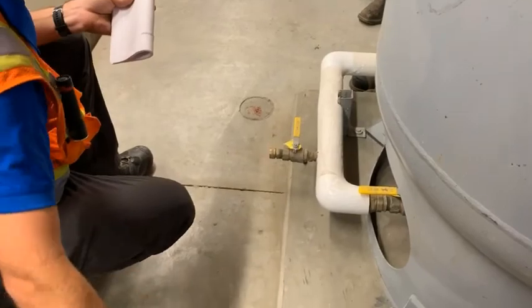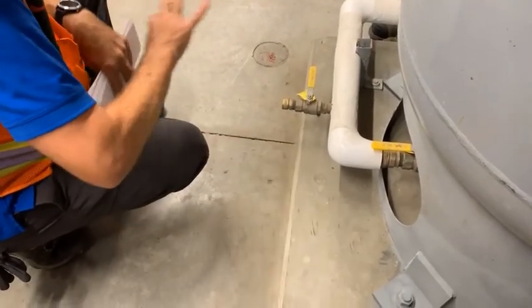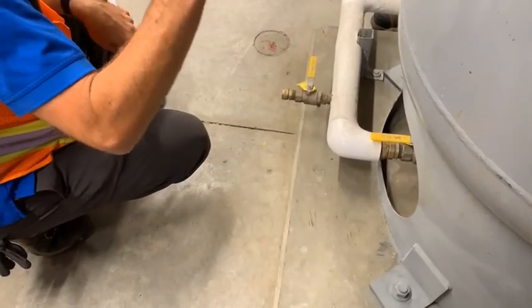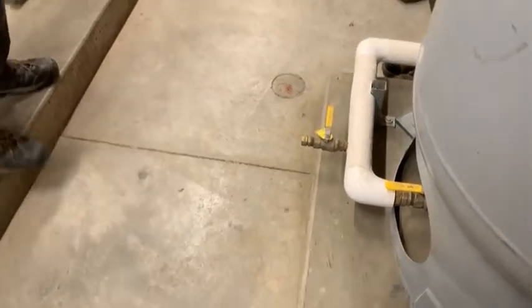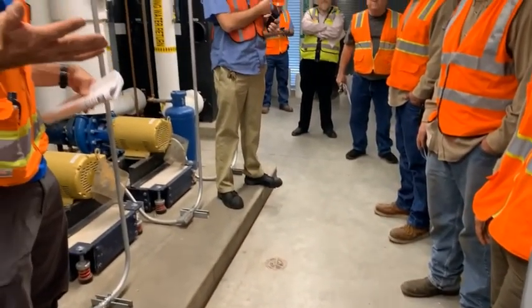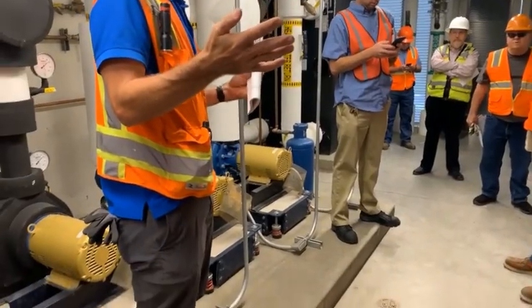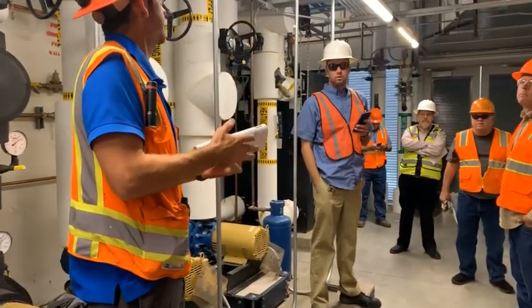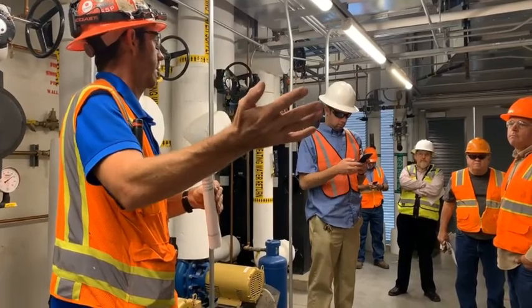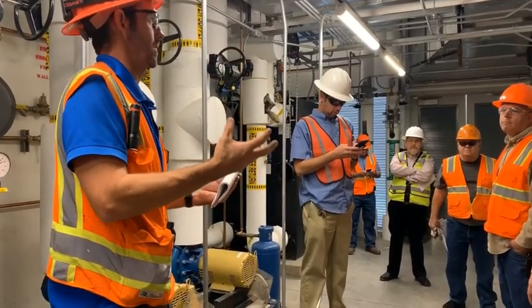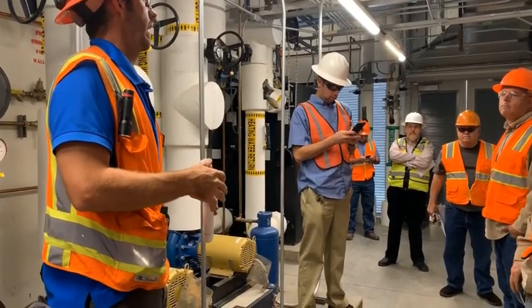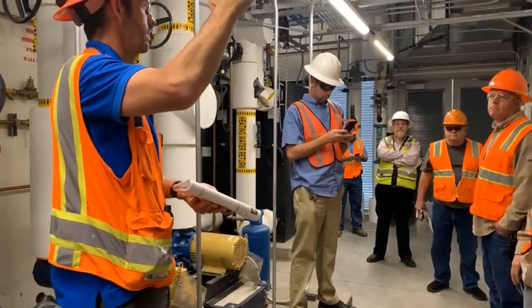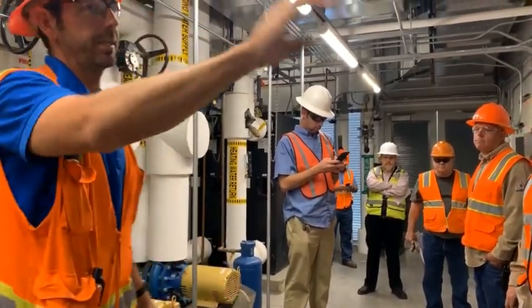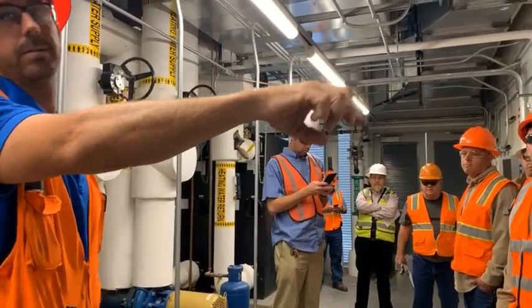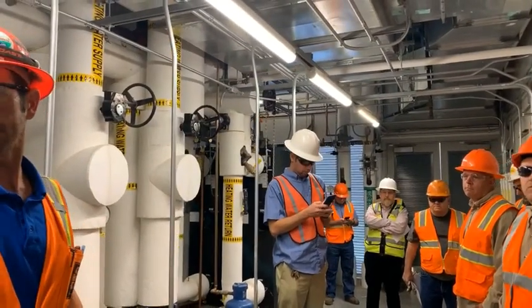Keep this guy open. Hook a hose here to the drain. Drain the pressure out of the tank, all the pressure out of the tank. You can't have any pressure in the tank to verify the nitrogen charge in the tank, okay? And then that gets me into the second point. We use dry nitrogen. If you use air, the different temperatures of air can affect the expansion tank setting. Nitrogen holds that pressure at a better temperature range than air does, okay? Again, this tank is set at 56 pounds. The domestic tank was 78, okay?